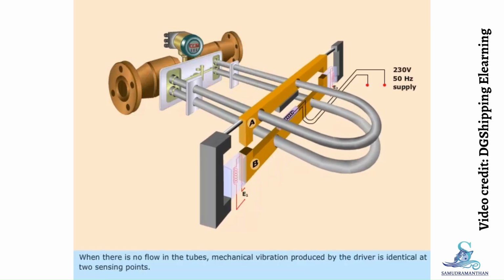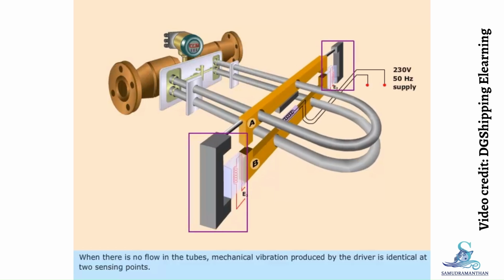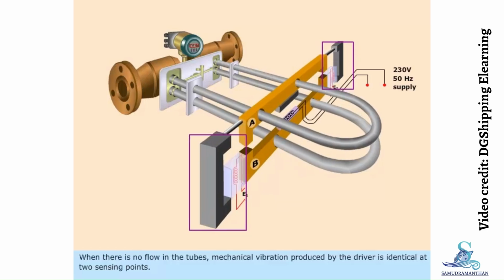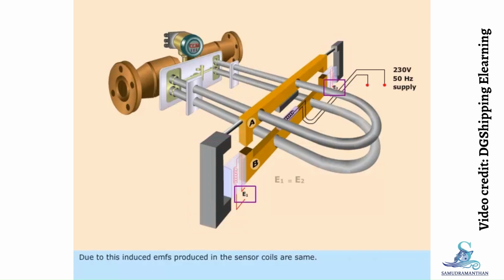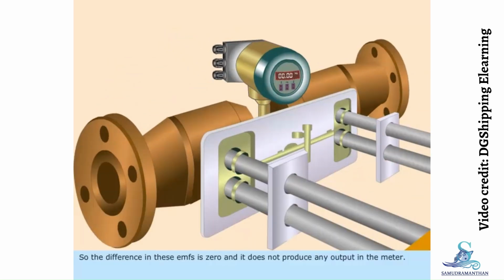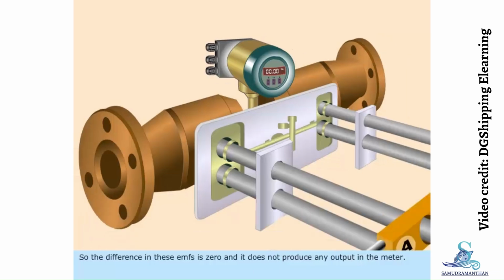When there is no flow in the tubes, the mechanical vibration produced by the driver is identical at the two sensing points. Due to this, the induced EMFs produced in the sensor coils are the same. So, the difference in these EMFs is zero, and it does not produce any output in the meter.